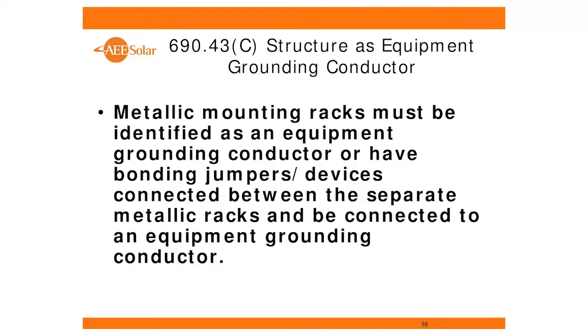So, grounding and bonding. At the end of the day, we did do some rewriting in 690.43. I think we did some nice cleanup. But when we leave the array, the equipment grounding conductor is going to go with our current carrying conductors. Within the array, the equipment grounding conductor is really allowed to take whatever kind of path it has to in order to do bonding and stuff like that.